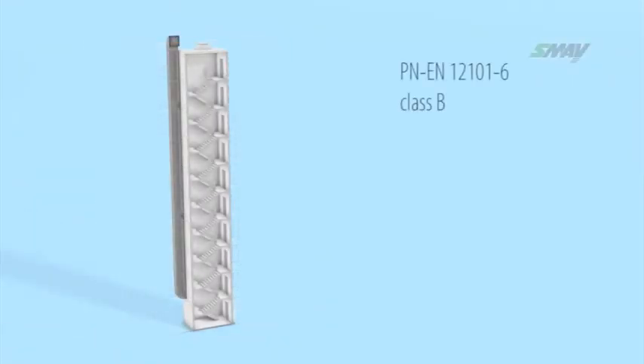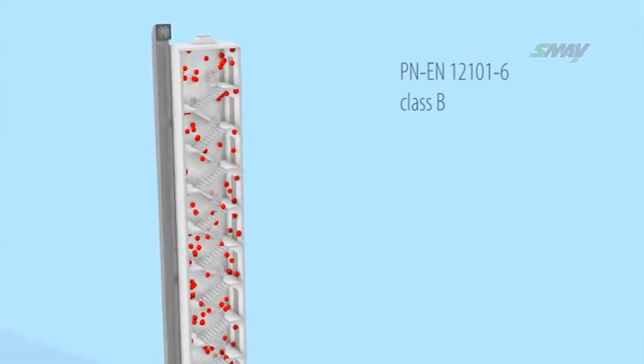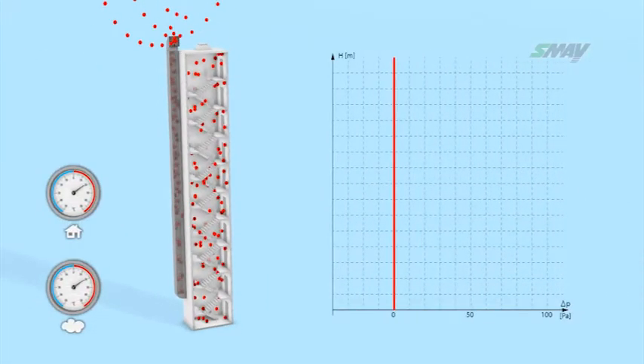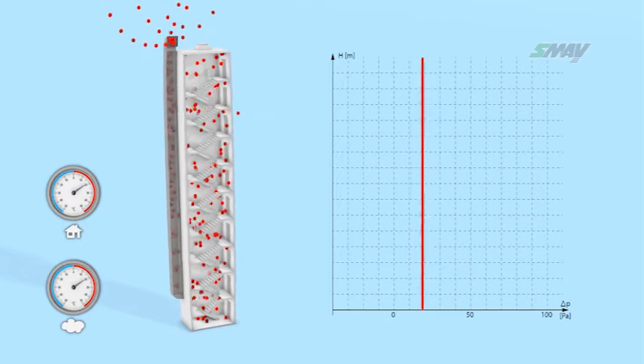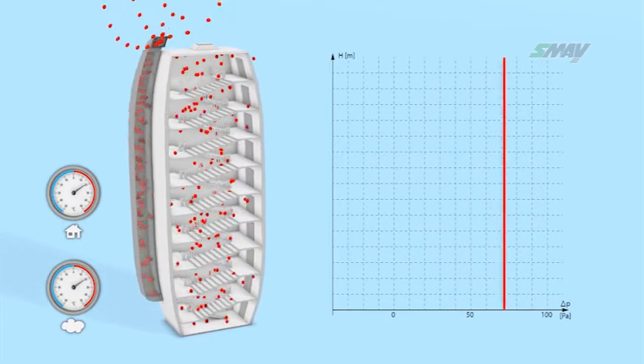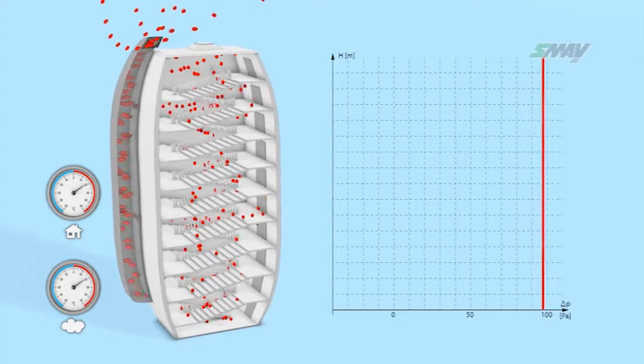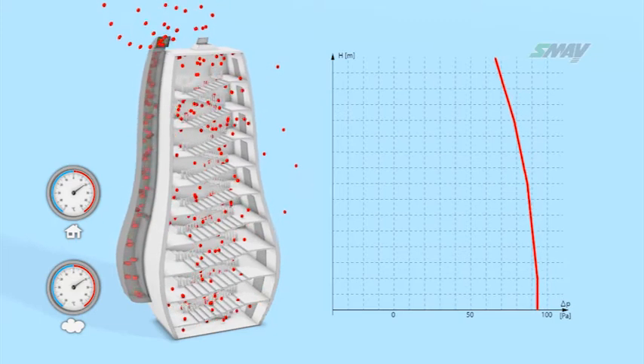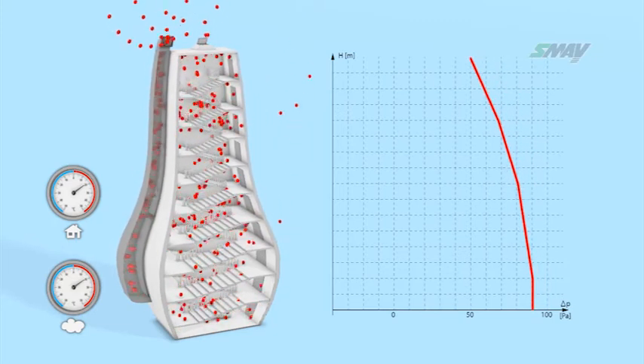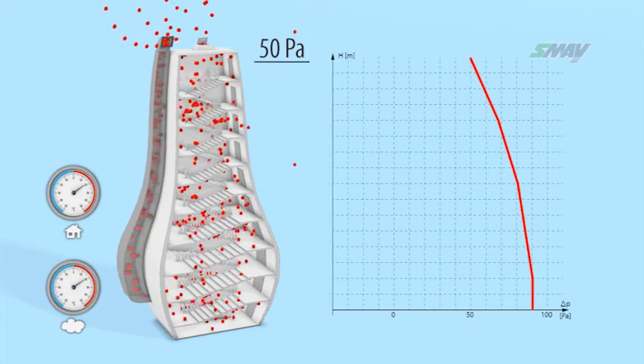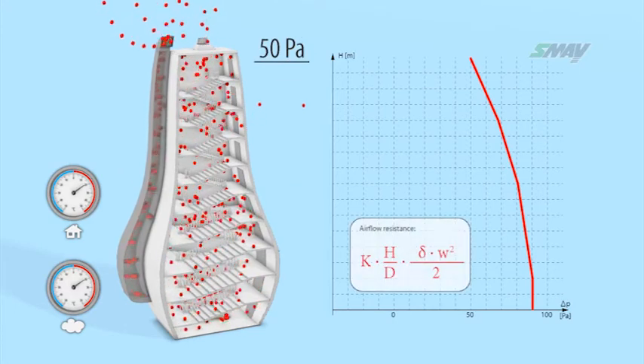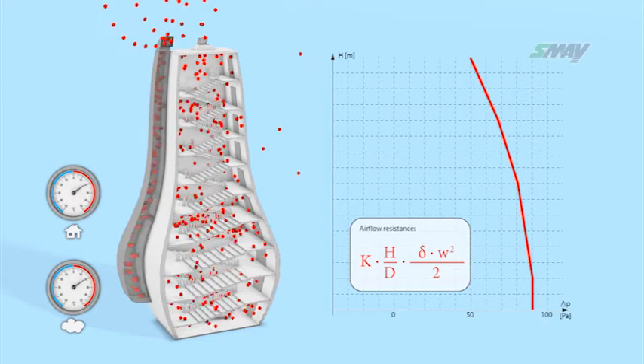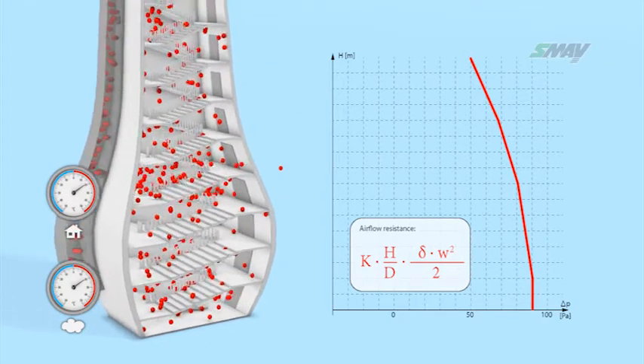Overpressure in the remaining parts is not controlled in any way and may fall to below the required minimum. If the building incorporates a class B solution in accordance with the EN 12101-6 standard requiring large amounts of air, then injecting the stairwell with air at the same temperature as the air inside the stairwell would initially cause a violent pressure spike along the entire height. The excessive pressure rise causes the barometric overpressure damper to open, maintaining overpressure in the upper parts at 50 pascal. The flow of large amounts of air causes resistance similar to normal ventilation ducts, and due to the resistance in the lower sections, overpressure exceeds the allowable value, which may make evacuation impossible.